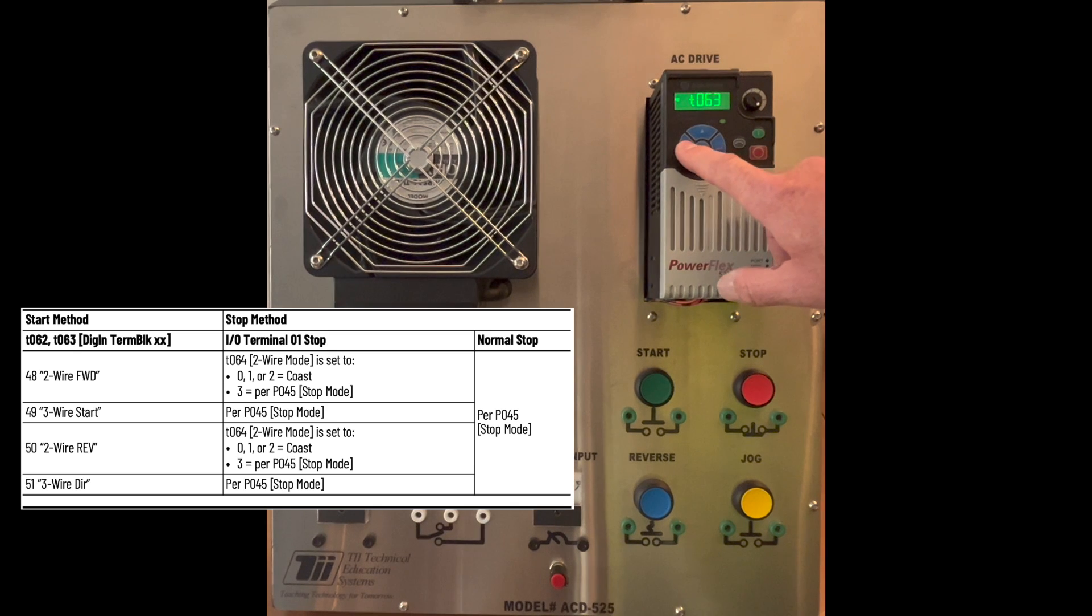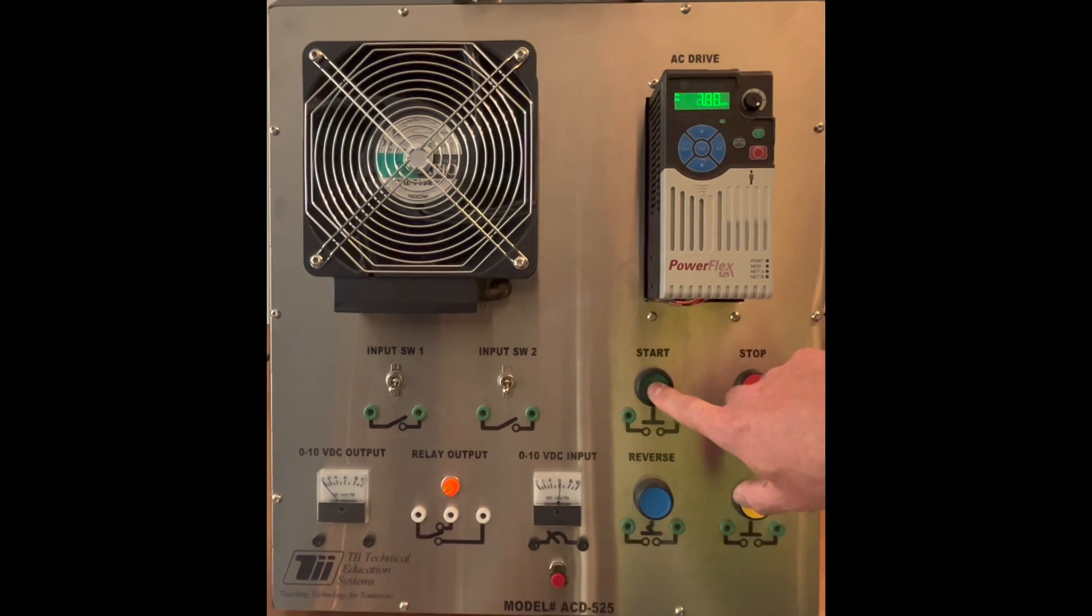And now we're going to see if this works. Activate the start button. The motor begins spinning, and it ramps up to the frequency that you have your keypad potentiometer set to. I can control the speed here, and notice it's just running, and I'm not pressing anything. That's why we know it's not two-wire control. Activate the stop button. That shuts it down.